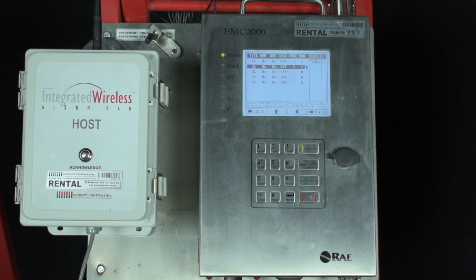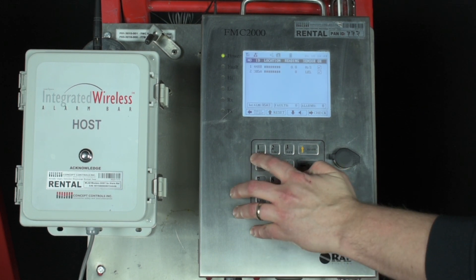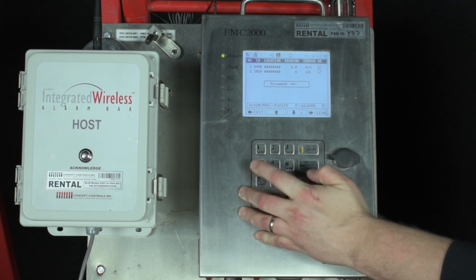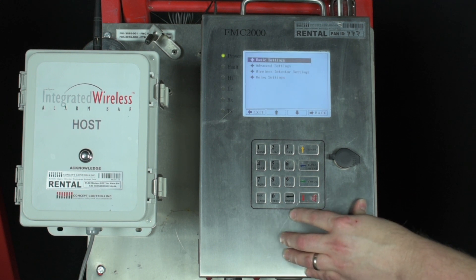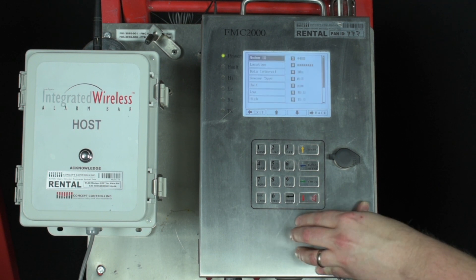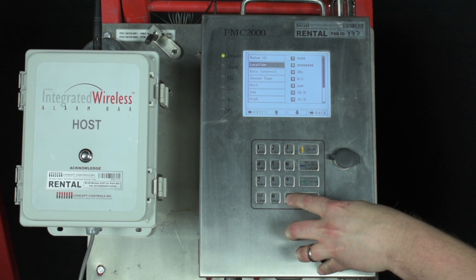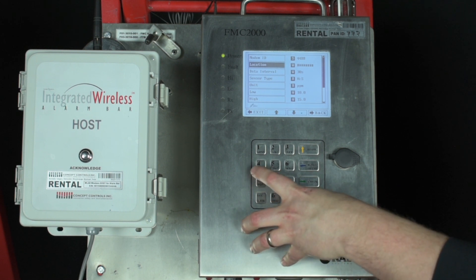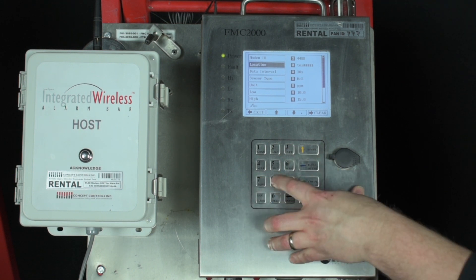Next we'll show you how to change the location names of the detectors. From the home screen press the menu button. Enter in your first tier password — it's 1234 by default — and press enter. Highlight and press enter on the basic settings icon. Scroll down and highlight wireless detector settings and press enter. From here you can press enter while module ID is highlighted to change the unit you have selected, then use the red arrow to scroll down to location and press enter. Use the letters on the number pad to state the location, press enter to accept, and the blue arrow to return back to the home screen.